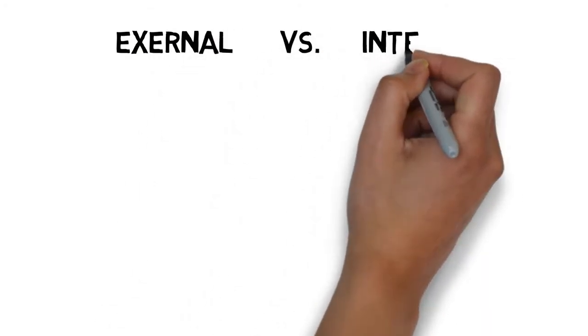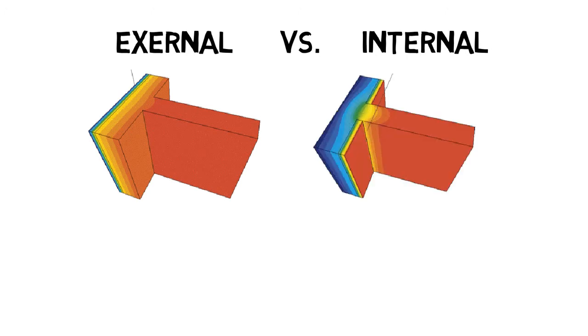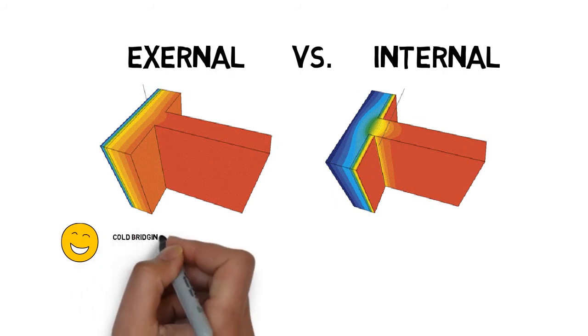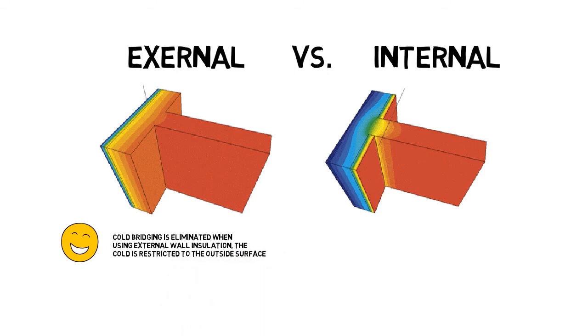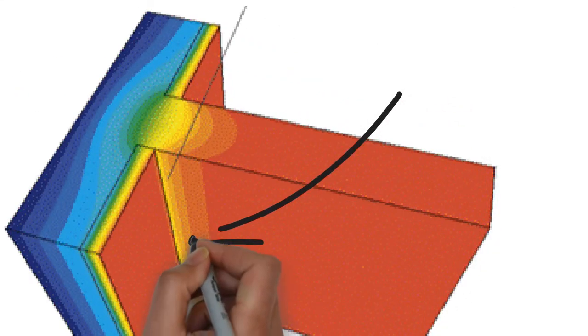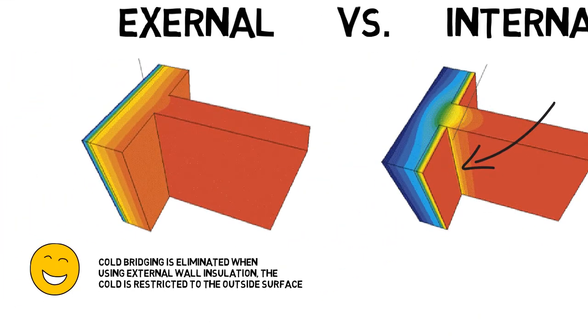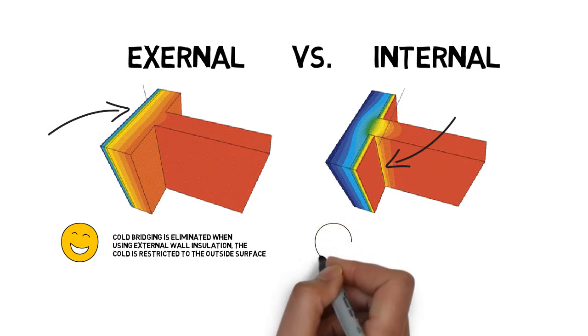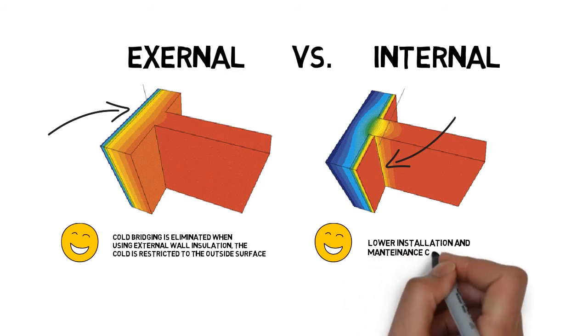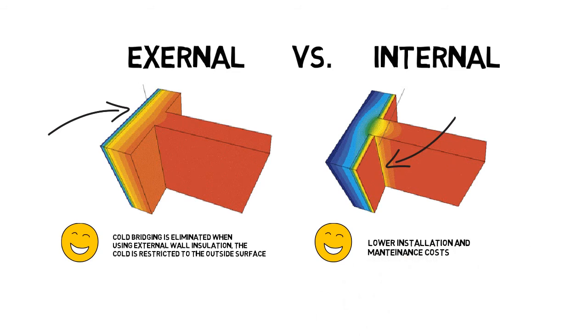Independently of the material, the insulation layer can be placed outside of the wall or on the inside part of the wall — this is the difference between internal and external insulation. Cold bridging can occur at partition walls when using internal wall insulation, but it is eliminated when using external wall insulation, where the cold is restricted to the outside surface. On the other hand, internal insulation has lower installation and maintenance costs, and both are commonly used depending on the climate.